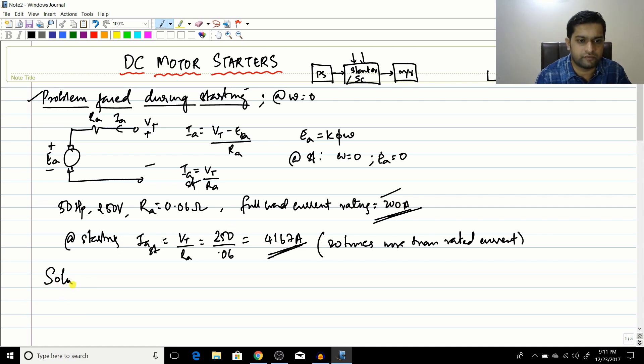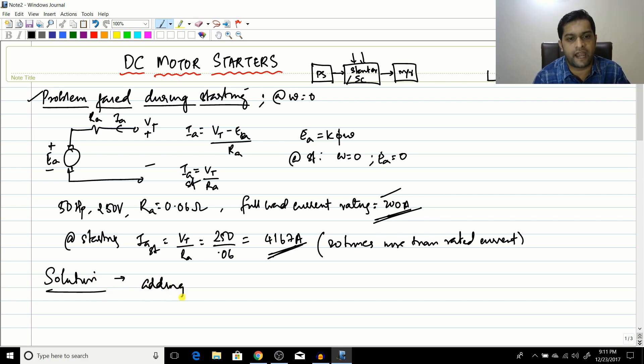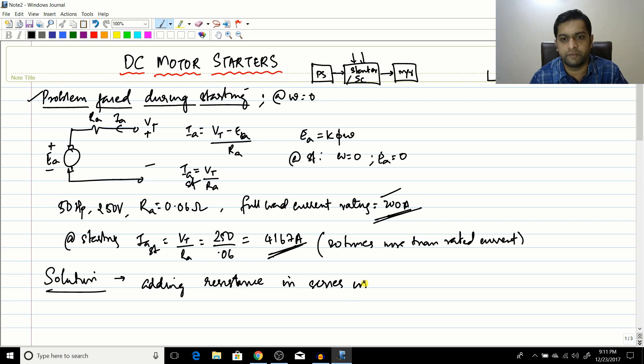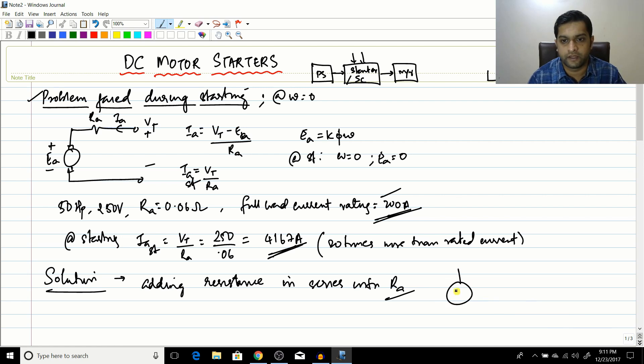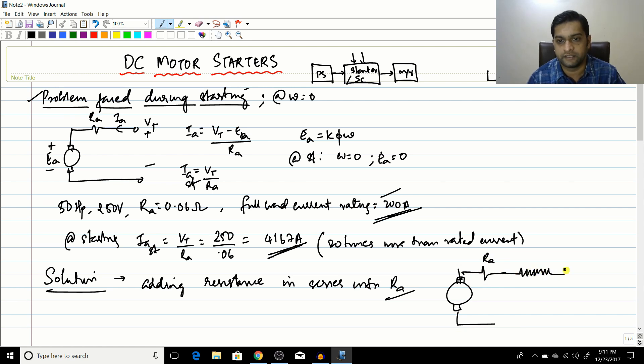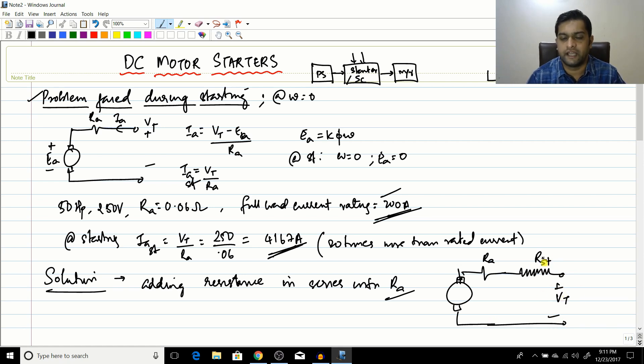The simple solution is to add a resistance in series with Ra — similar to what we saw in speed control. You place a starting resistance, R_start, in series so that the current is brought down to a manageable value.